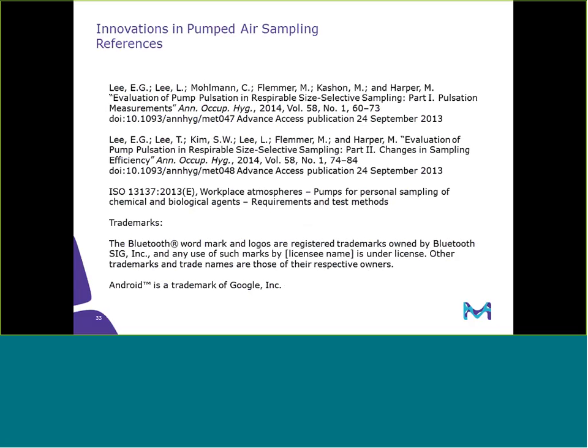We have a question from Lucinette. She asks, if the pump will have its own calibration device, will it require an annual calibration from the manufacturer, as in the case of the primary calibrators available? Yes, it would still need to be calibrated annually, as with any calibration device. According to all the manufacturers, the recommendation for any pump is to have that pump sent back and calibrated. Also, that calibration device requires calibration every year. So essentially what you're doing is you're calibrating two devices, but you only need one device to do a calibration.